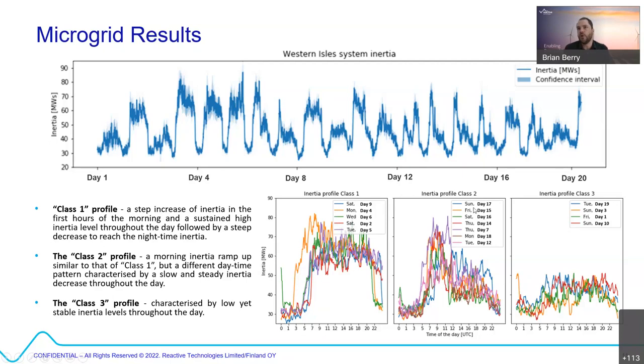Well, no. Because if you look here, you've got Sunday, Friday, Monday, Tuesday. This one's got a Saturday. This one's got a Wednesday, a Monday. This one's got a Tuesday, Sunday. It's not like that. There's no pattern to this, because it's dependent very much on the generation and the industry that is running at that particular time. Now, when we talk about training inertia models from demand curves and capacity curves, and tuning them with events that happen, let's say, 3 to 5 times a month, it's not enough to capture these intricacies. So that's just one very interesting output we found: the different profiles in the grid.